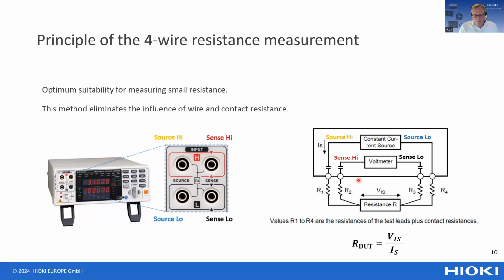The 4-wire measurement method works like this: the source signal, the AC source current, is connected through wires on the outside, so the measurement current flows through this circuit. At the same time, the voltage of the battery is measured with a voltmeter inside the battery tester. The internal resistance of this voltmeter is very high, meaning that in this circuit there is almost no current flowing. Because there is no current flowing, there is also no voltage drop over the connections, meaning we can accurately measure the voltage over the battery.